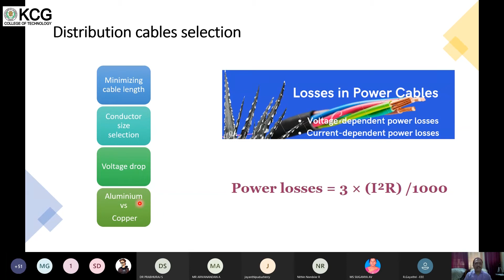Similarly, while selecting the conductors, it is very important to understand what is the voltage drop at the other end. So all conductor selections will be based on the voltage drop. Industry norms work on a 4% drop in voltage being permitted. Anything more than that unnecessarily affects the operating equipment because the terminal voltage drops below the efficient voltage level. Similarly, we have opportunities to improve the performance by choosing copper conductors rather than aluminum conductors. But then it is an economic issue when it comes to procurement in industries, and therefore nothing much can be said about it. But we can discuss, any one of you interested, either now or in the future when you go and work in an industry, if you see an opportunity based on what I am now sharing with you, we can discuss this as we go forward.